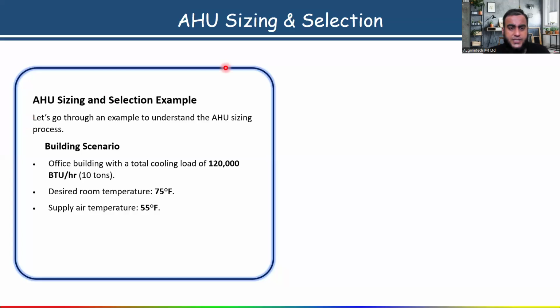Okay. So now come to our main topic, which we are talking about. So here I'm talking about the AHU sizing and selection example. So the building scenario is given, office building, their cooling load value is given 1,20,000 BTU per hour, okay, means sensible load. Desired room temperature 75, supply air temperature is also given, 55 degree Fahrenheit.